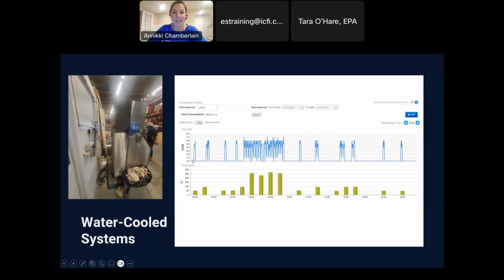The system needs to be cooled. The compressor comes on, it's cooling the space. Boom, I've got water flow to cool off the condenser. The compressor comes back on, and water starts running to cool the condenser. So this is what a normal water-cooled system should look like: on and off, on and off, on and off, as it needs to remove heat.